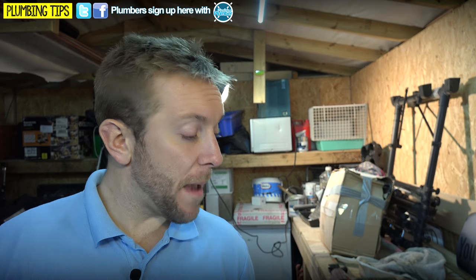Anyway, I hope you enjoyed today's video. I hope it's given you a better idea about how these little beasts work, about how you can deaerate the system. There are many other ways of doing it. We're going to look into automatic air vents on pressurised systems as well. I mean, you can have automatic air vents on unvented systems as well. There's nothing wrong with that. It's just, when you're near the pump, especially if you put the air vent on the suction side of the pump, you can get problems with the air vent, like float dropping, and actually sucking air into the heating system. It's quite rare, but it does happen. So there's a few little different things that can go wrong. But it's so important that the system is deaerated properly. So, again, I hope you've enjoyed today's video. I hope you've learned a little bit more about how you can deaerate your system. Please do subscribe to this video by clicking on the link that's appearing right now in cards. Thank you all. And please do follow us on Twitter and Facebook, because if you're not, you're missing out on stuff like this.